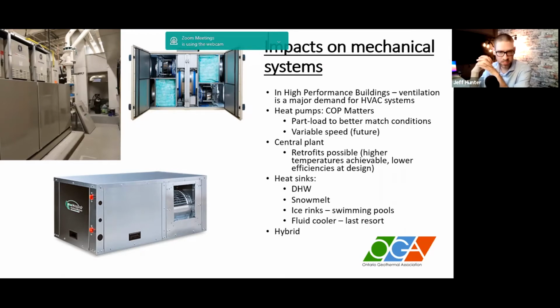Central plants can be retrofitted to heat pumps these days, and heat pump technology does allow for higher temperature applications. Let's say existing buildings with higher temperature baseboard radiators distributed throughout the building, we can meet those higher temperatures, but we need to be conscious of the lift the heat pump needs to take the source energy to the heating temperature for those rads. It just impacts the efficiencies of that equipment.